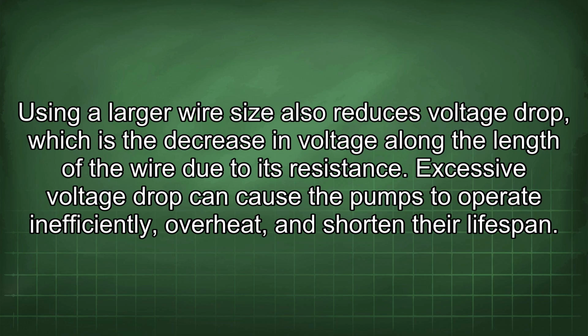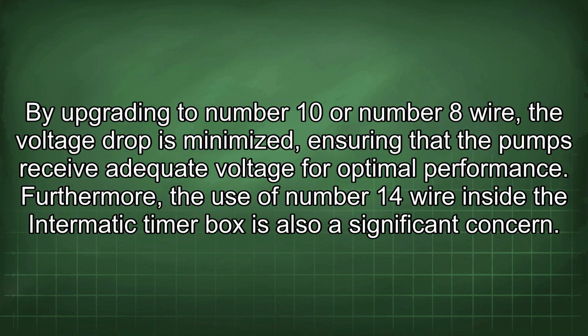Excessive voltage drop can cause the pumps to operate inefficiently, overheat, and shorten their lifespan. By upgrading to number 10 or number 8 wire, the voltage drop is minimized, ensuring that the pumps receive adequate voltage for optimal performance.